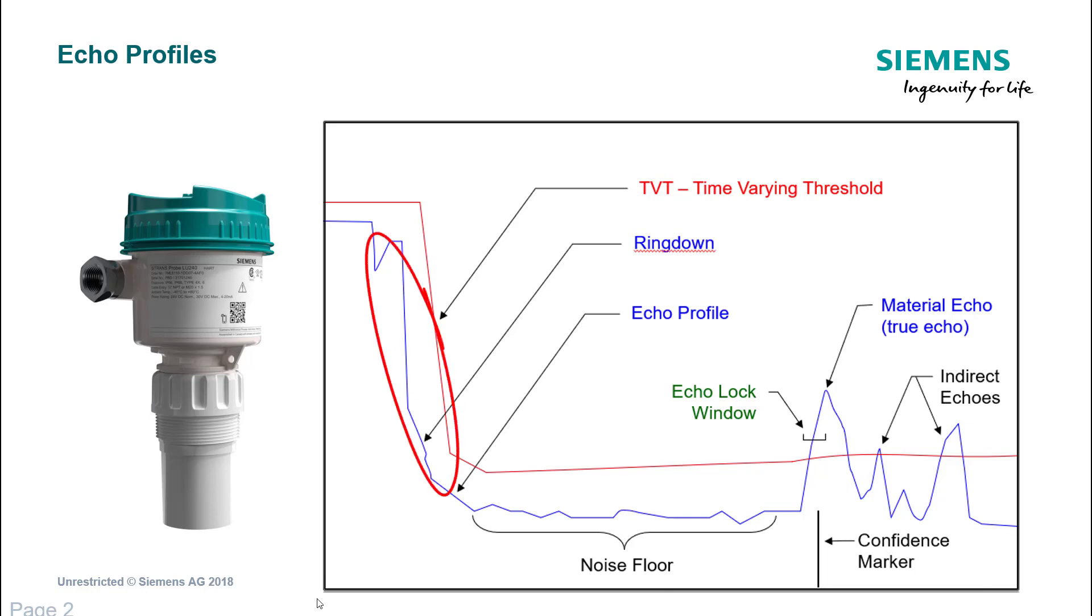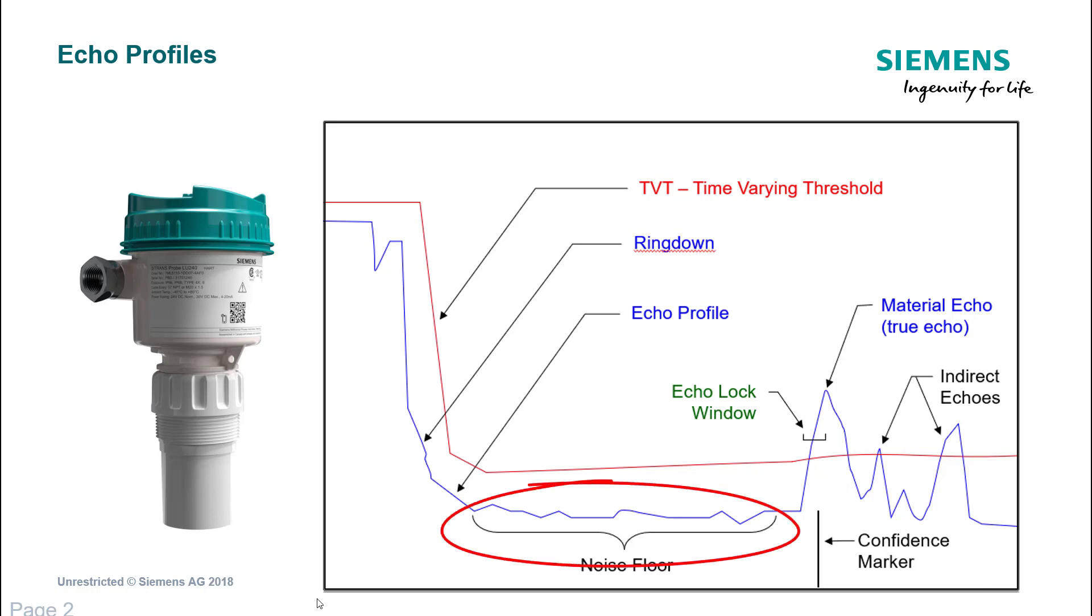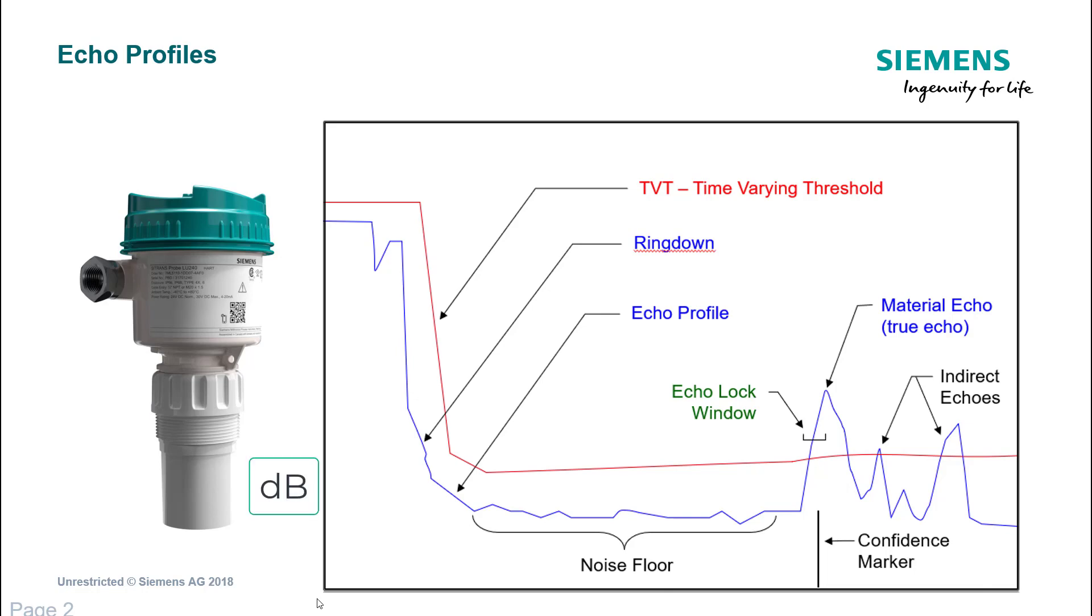This is normally on ultrasonics where the near blanking comes into account. The signal then drops to its lowest point which we call the noise floor. Ideally that noise floor will be zero decibels, so the value on the left hand side, the y-axis, is decibels.